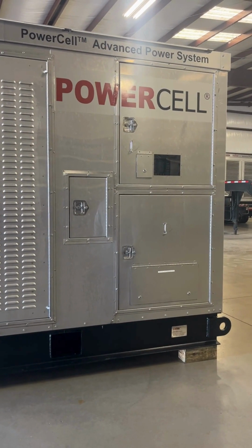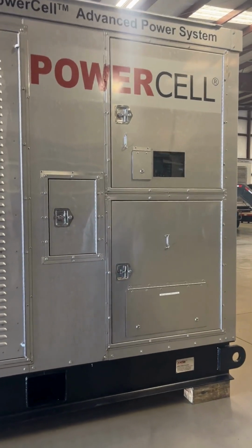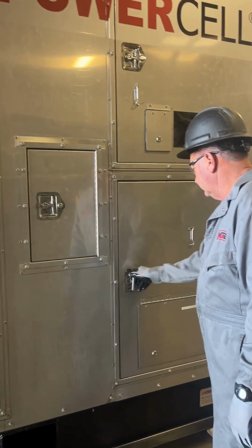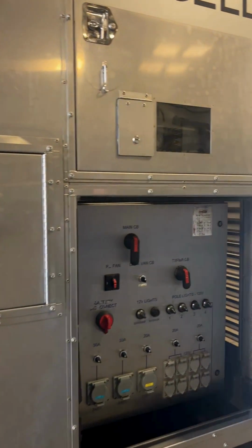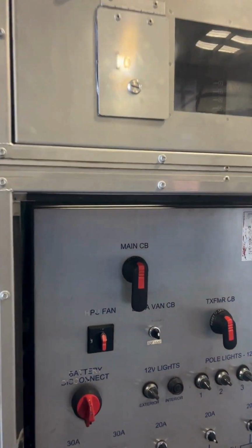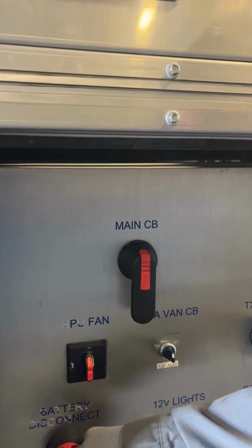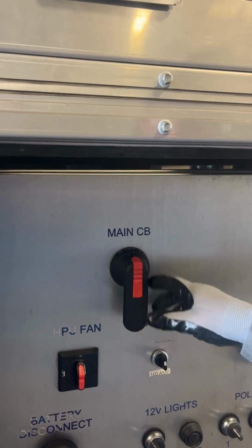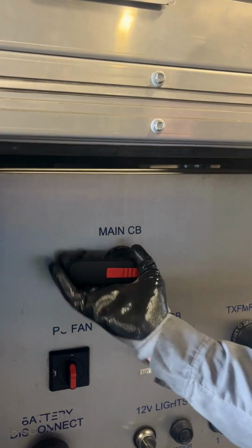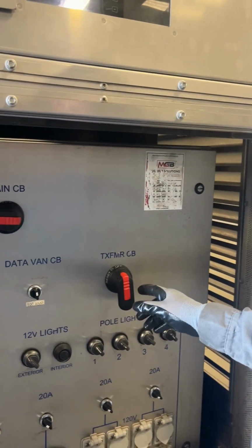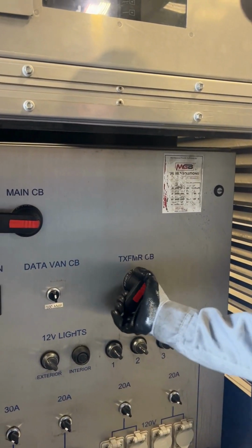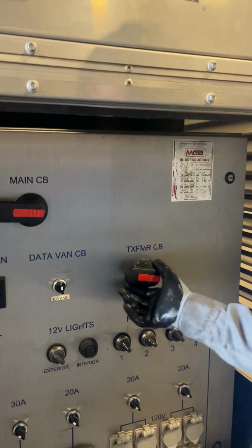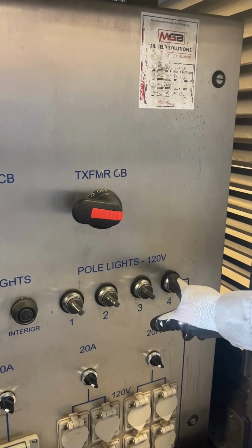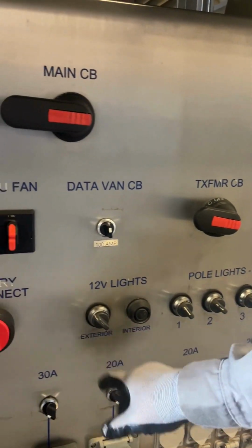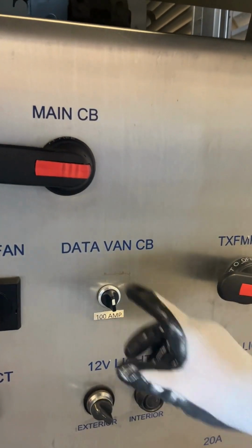Today, we're going to go through the basic steps on how to start the PowerCELL. We first open up the bottom right door, and what we're doing is making sure that all our circuit breakers and switches are in the correct position. So the main circuit breaker is in the on position, and the transformer, which is the 480 to 240 volt, is in the on position. Make sure all your other switches are in the off position, as well as your data van circuit breaker.